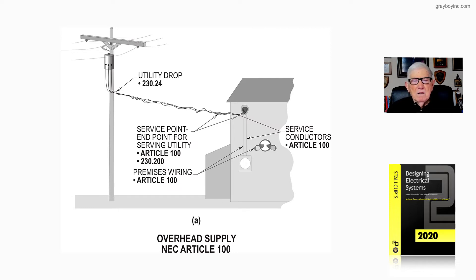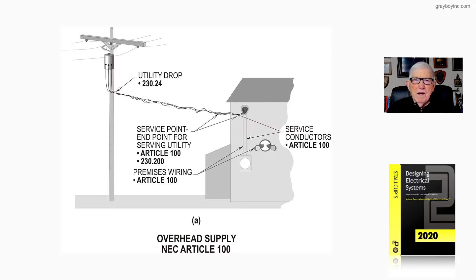Now, basically, it's a service drop if the utility owns the transformer and the distribution lines. If they are owned by the owner, then this would just be considered service conductors that you see from the transformer to the building.